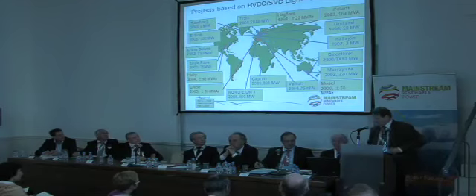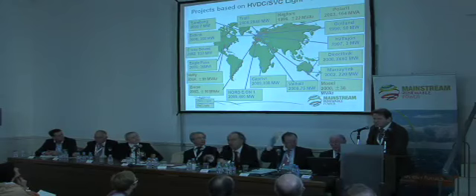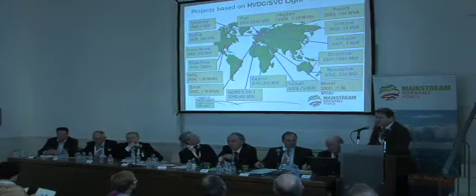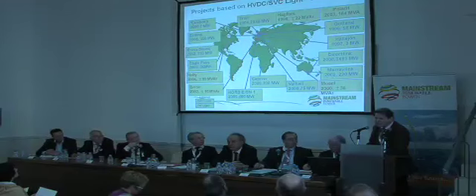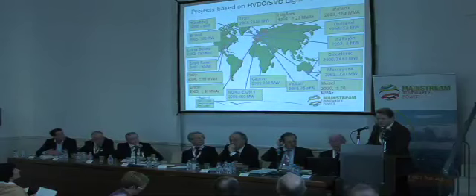These are all projects done with the new technology of HVDC, which is very suitable for building grids. That is the voltage source converter technology. We have already been working with this since 1997, and we have many projects all around the world, demonstrating that this technology is now mature. It had somewhat high losses in the old days. Now the losses are down below 1%, close to the same losses as the classical HVDC. And the power ratings are going up, so we can build 2,400 megawatt transmissions with this technology.